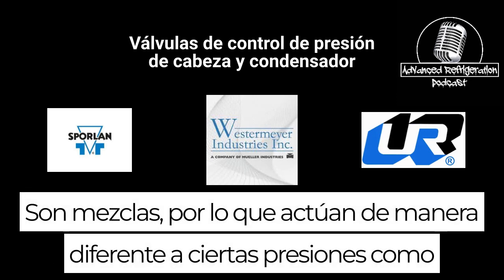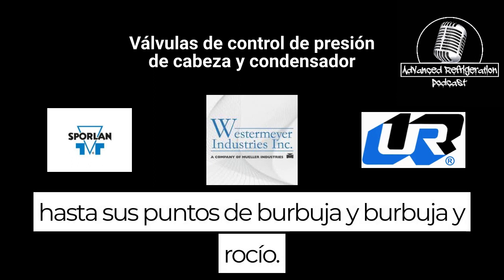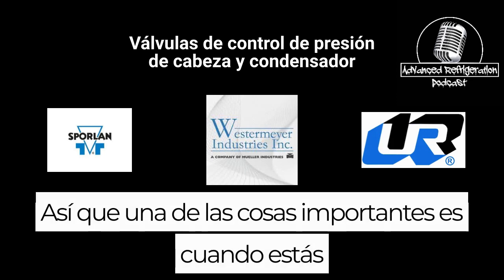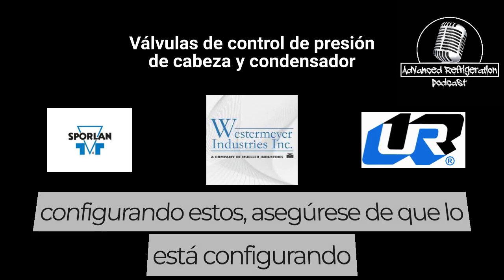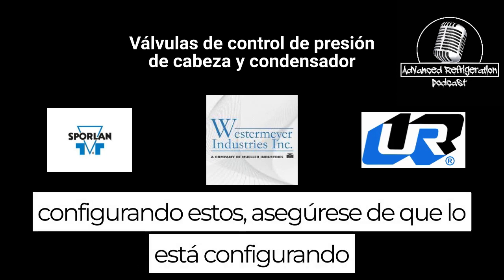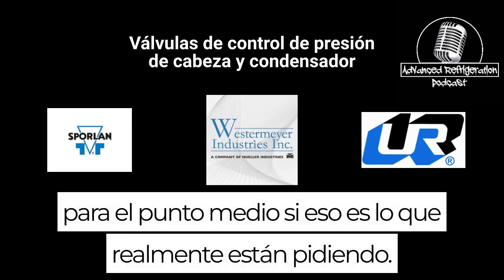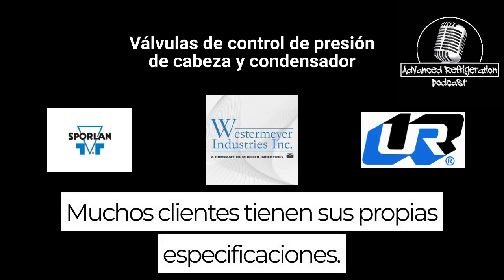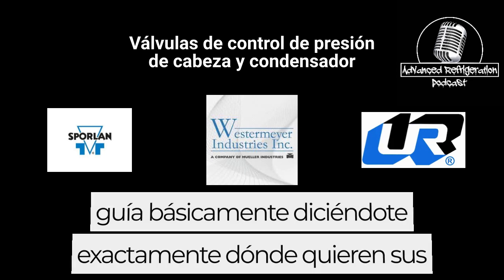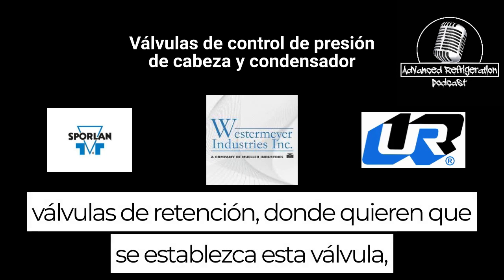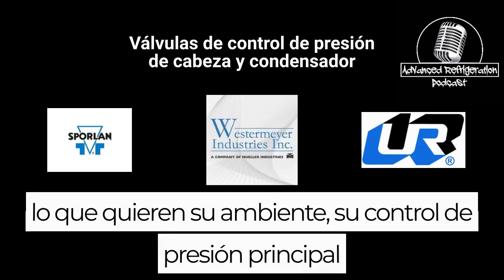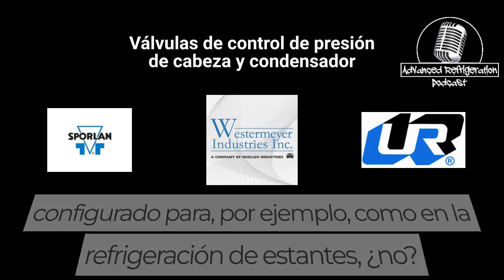They're blends, so they act differently at certain pressures as far as their bubble and dew points. So one of the important things when you are setting these up is to make sure that you're setting it up for midpoint, if that's what they're actually going for. A lot of customers have their own spec guide, basically telling you exactly where they want their holdback valves, where they want this valve set, and what they want their ambient head pressure control set for.